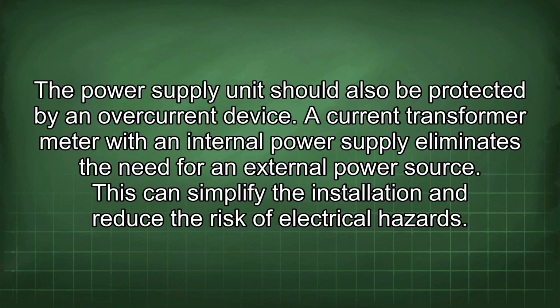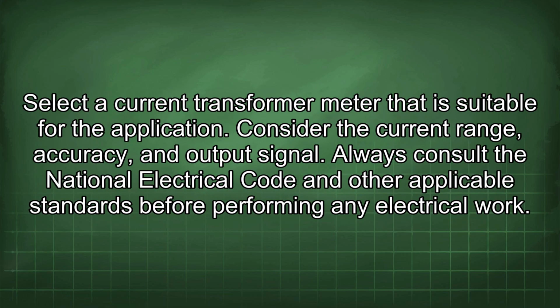A current transformer meter with an internal power supply eliminates the need for an external power source. This can simplify the installation and reduce the risk of electrical hazards. Select a current transformer meter that is suitable for the application. Consider the current range, accuracy, and output signal. Always consult the National Electrical Code and other applicable standards before performing any electrical work.